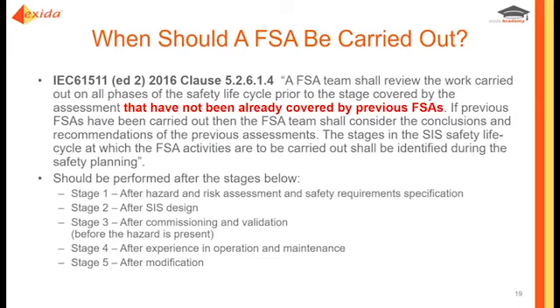So, as I tell students in the classes all the time, these 5 functional safety assessments are there for a reason. You need to do them because it provides you with a safety net. So stage 1 would be done after the hazard and risk assessment and the initial safety requirement specification. And what you'd be looking for there is to make sure that the hazard and risk assessment was done correctly, the LOPA was done correctly, that we have the right number of SIFs, and that the SRS reflects correctly the requirements. Stage 2 is after you've done the design.